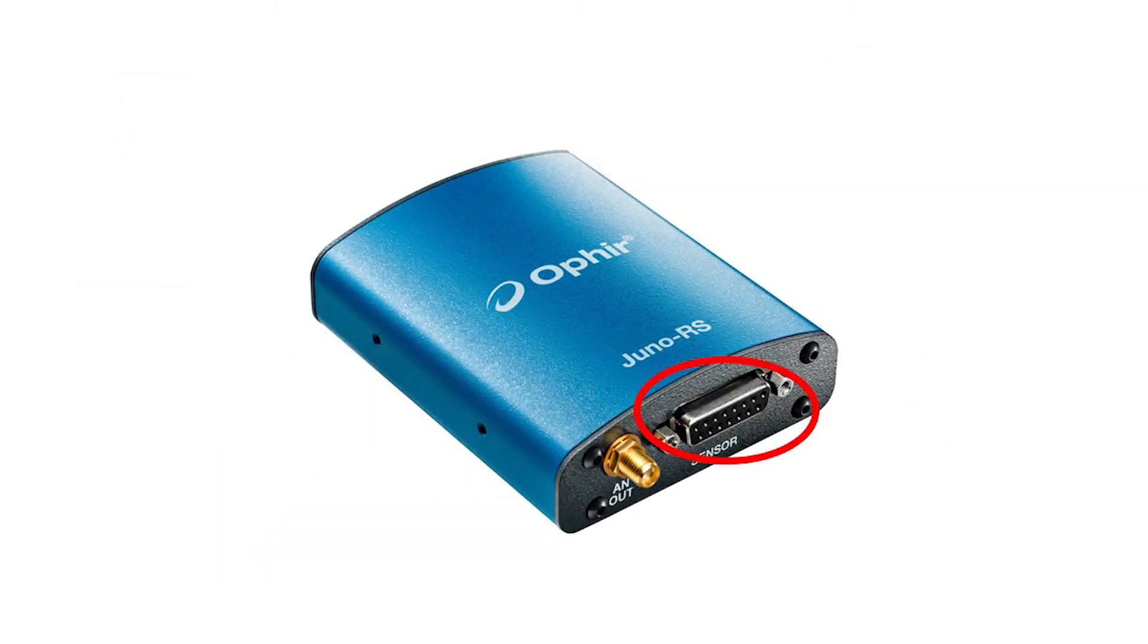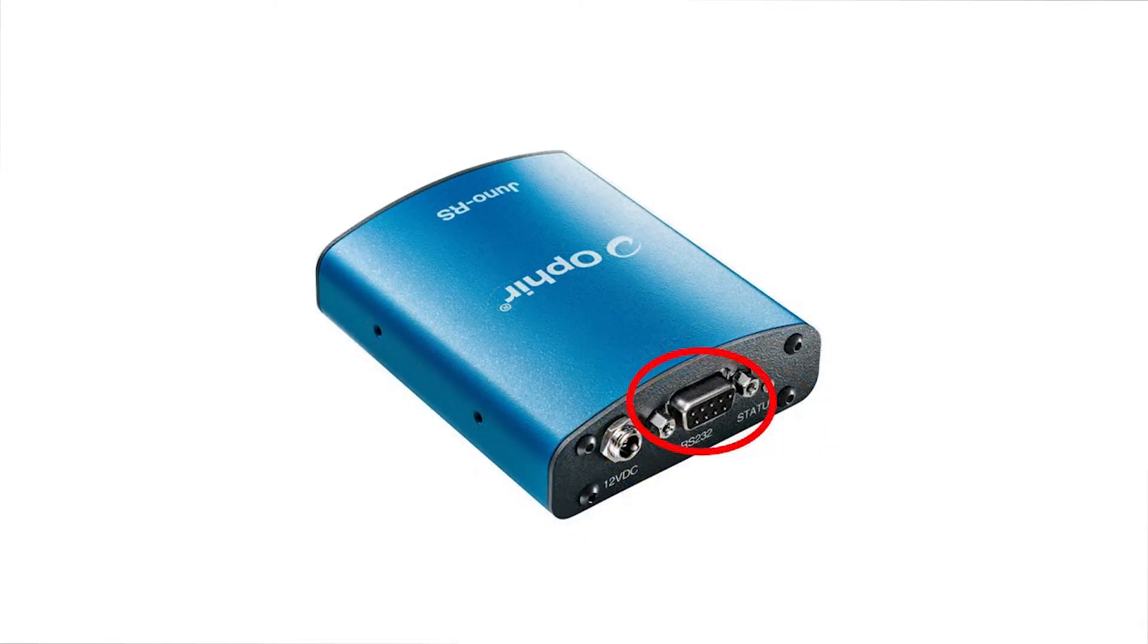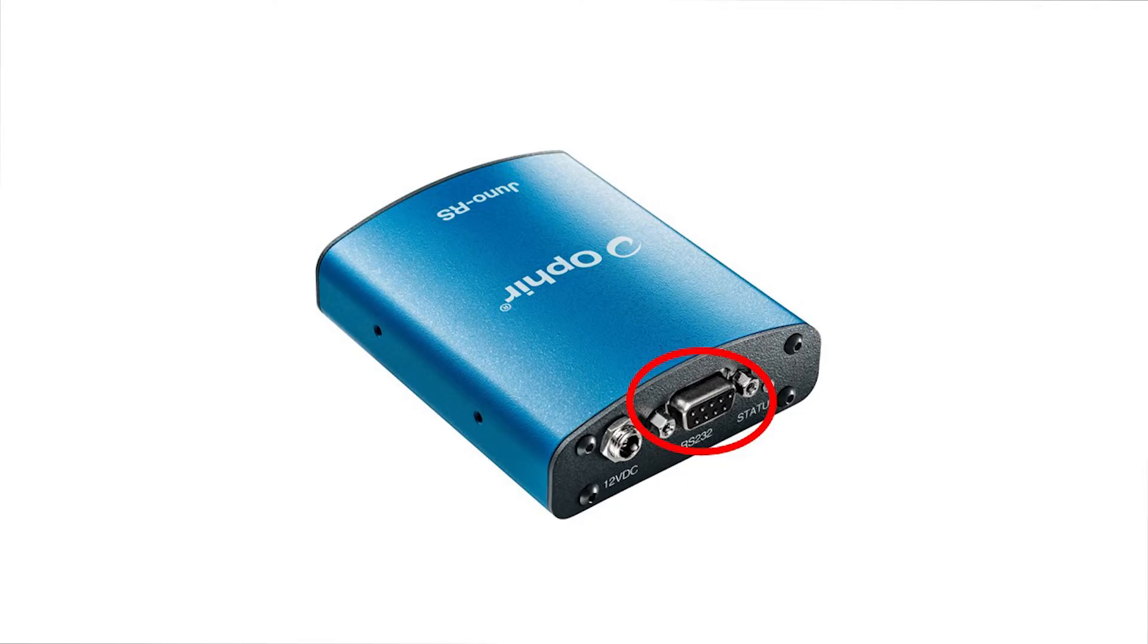Here you connect the sensor's DB15 smart connector, which contains the sensor's calibration and related data. Here, on the other side, we can see the DB9 connector through which the RS-232 interface is provided.